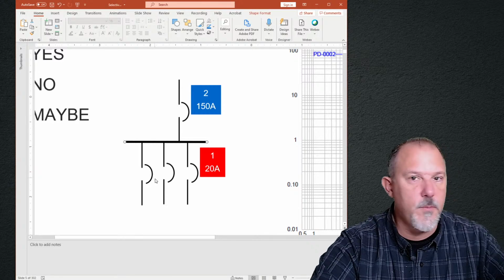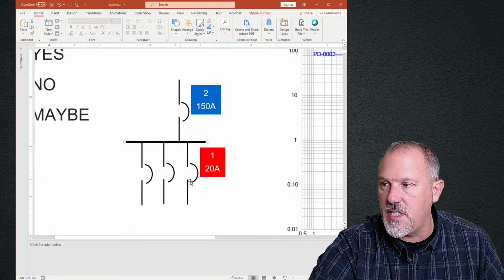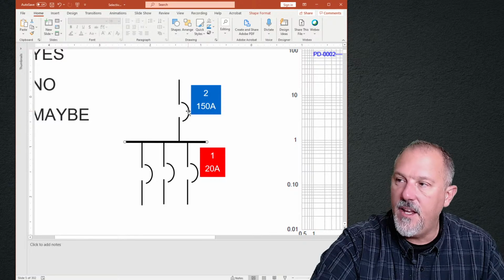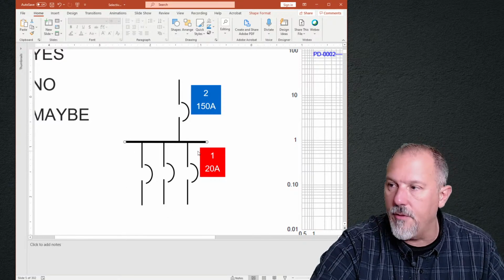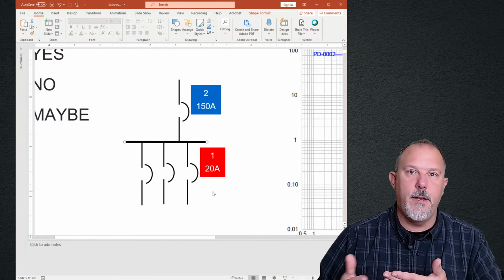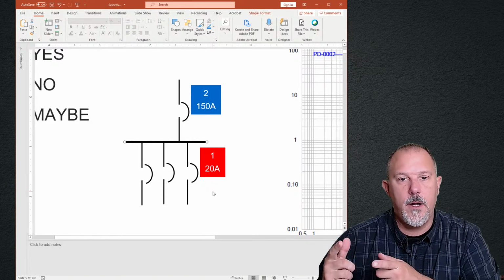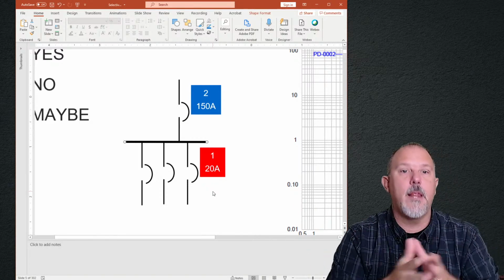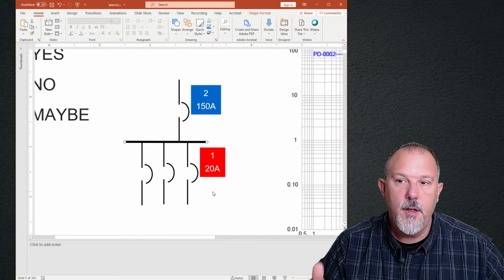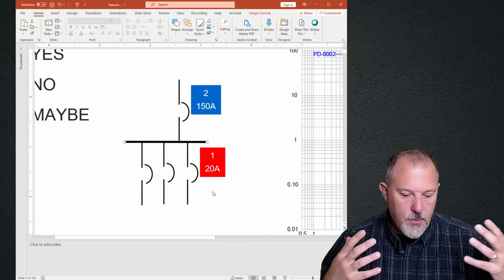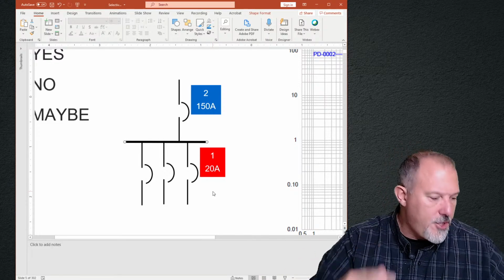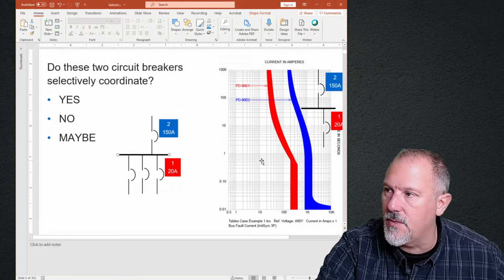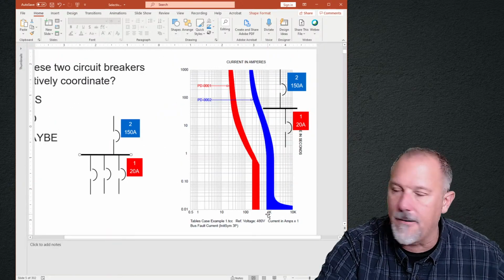I could have multiple 20 amp circuits. I could have two 15 amp and one 20 amp. If I take that breaker out, I lose all three of those, not just that one. So I was only showing one breaker, but in reality, we know that panel board's going to have more than one breaker.